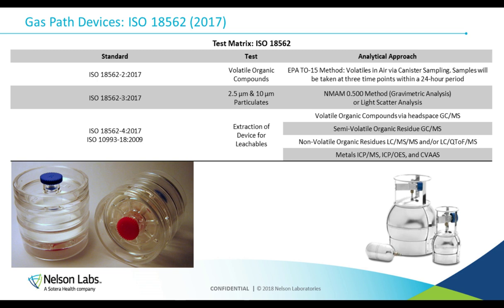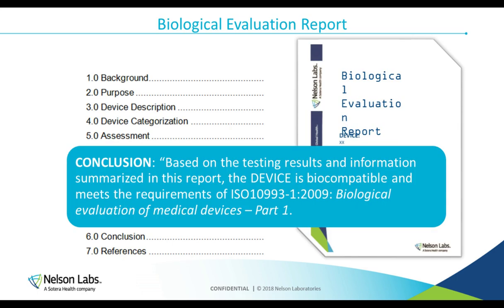Briefly, the particulates are tested either by directing gas through the device and collecting particulates on a filter, or it can be done with light scattering techniques. Volatile organic chemicals are captured and analyzed by directing clean gas through the device and then sampling into a vacuum canister that's then analyzed using standard methods that are well validated within the environmental chemistry arena.